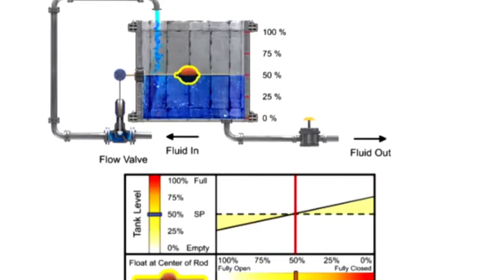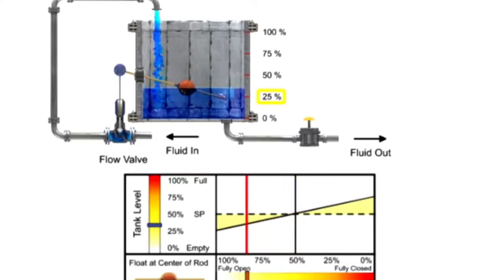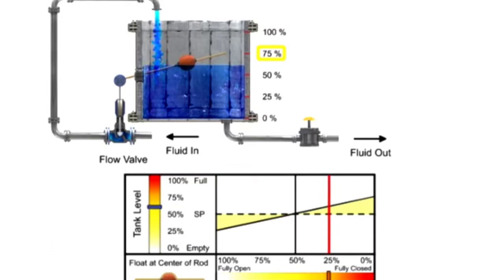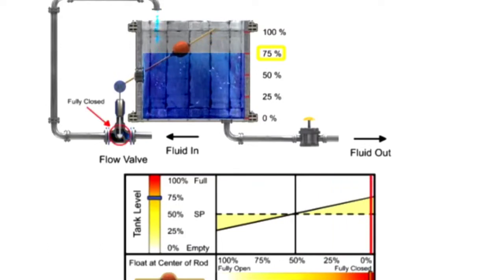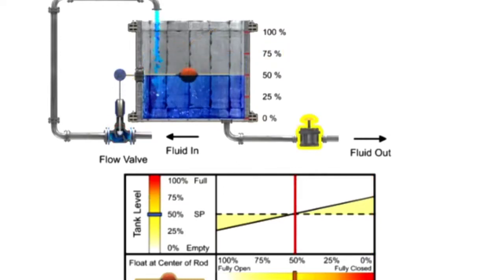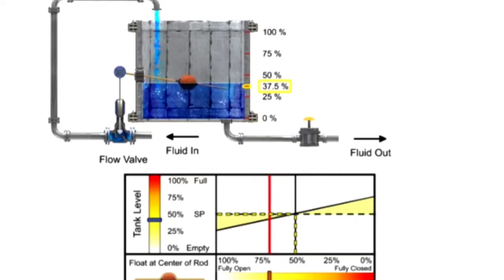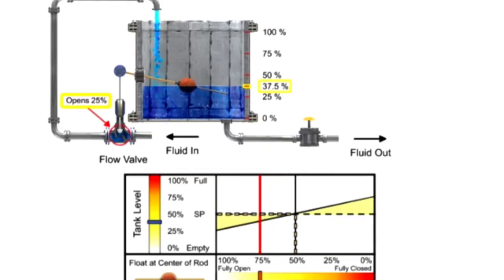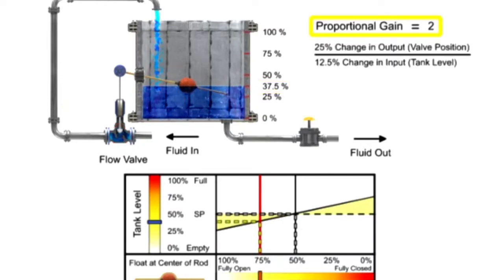Positioning the float to the midpoint of the bar increases the gain. The valve fully opens when the level drops to 25% and fully closes when the level rises to 75%. Opening the drain valve causes the tank level to drop by 12.5%, or to 37.5% full. The float drops and the valve opens 25%, demonstrating a gain of 2, since the 12.5% change of tank level resulted in a 25% change of valve position.